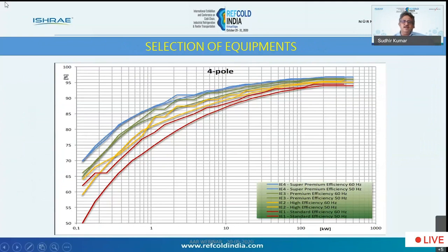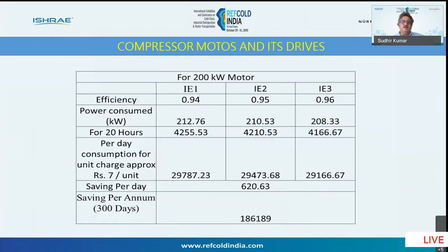These are some of the efficiency curves which are used for the motors. I have just given you a small comparison for a 200 kilowatt motor. If you see, IE1 is about 0.94, whereas IE2 is 0.95 and IE3 is about 0.96. So you will be saving power of about 2 lakh rupees per year. So definitely use an IE3 motor, even in your existing plant. If you have an old plant and the motor is already rewound 3 times, it is better to shift to new motors, because the efficiency is down if you are rewinding the compressor motors.